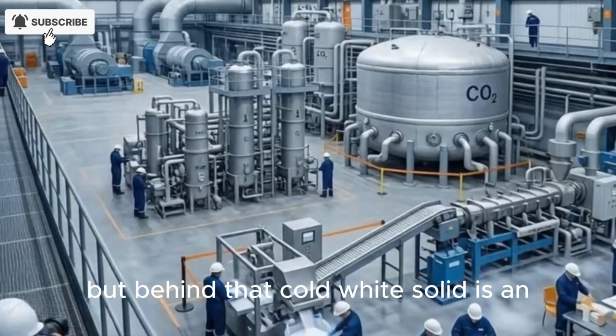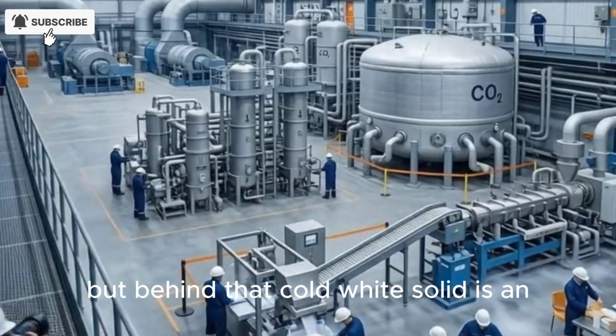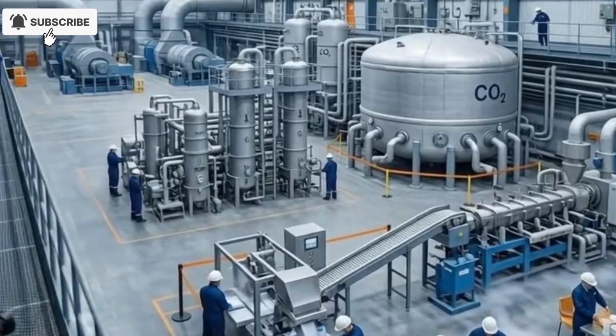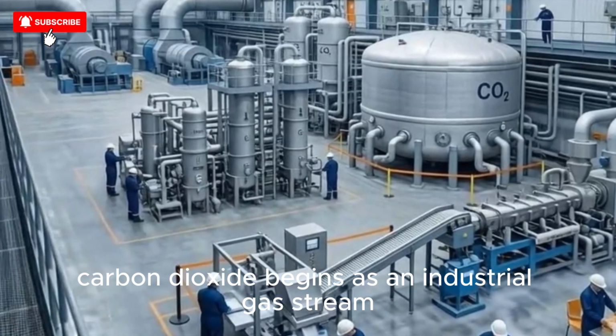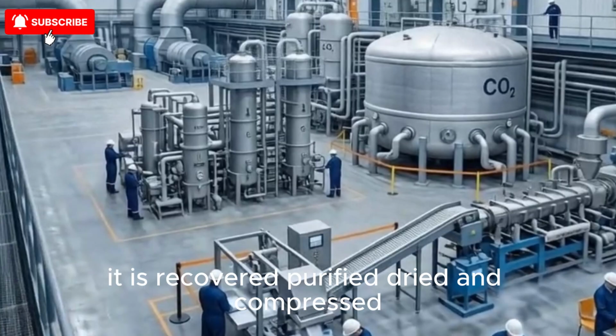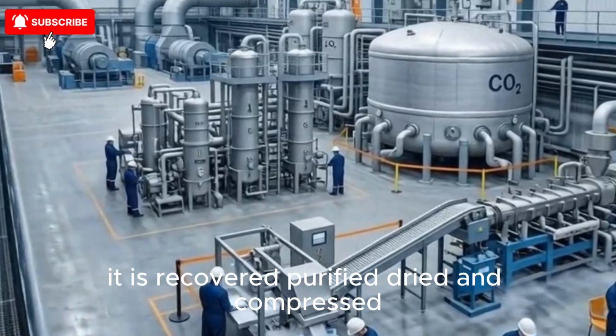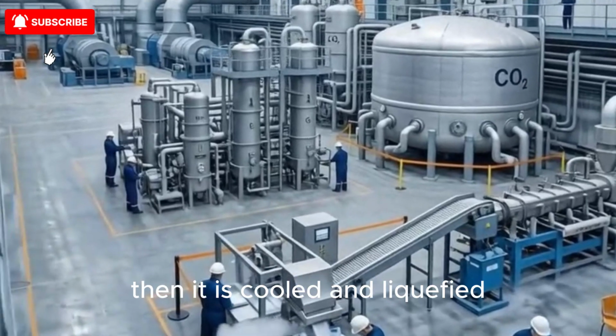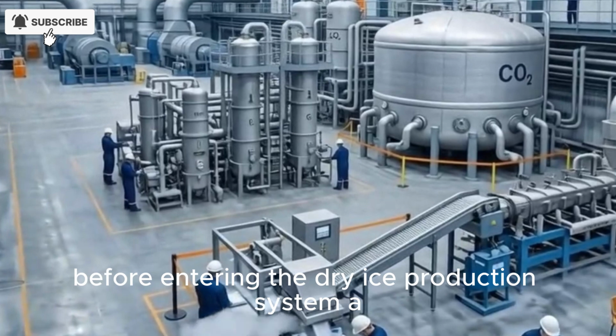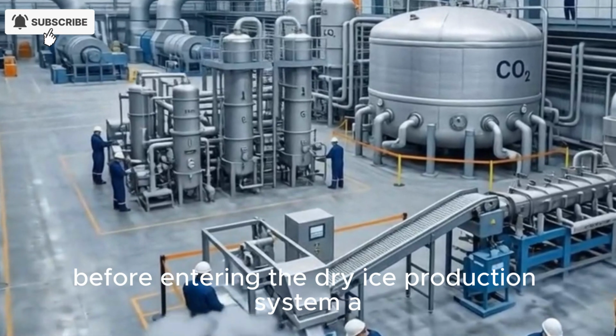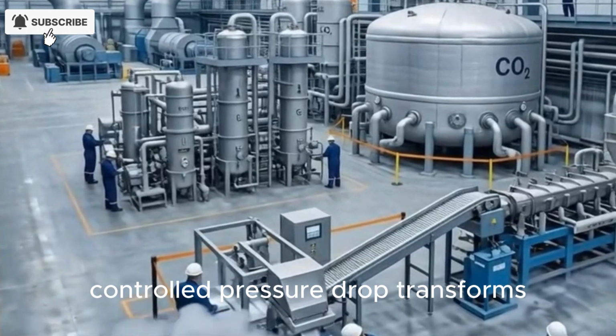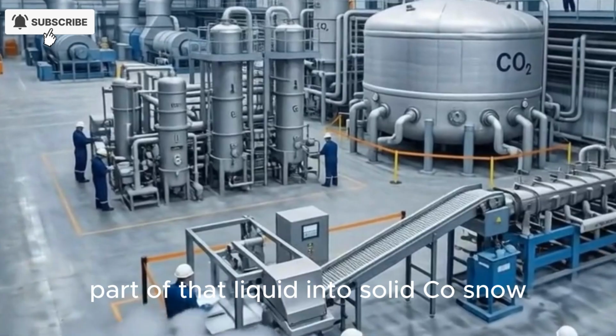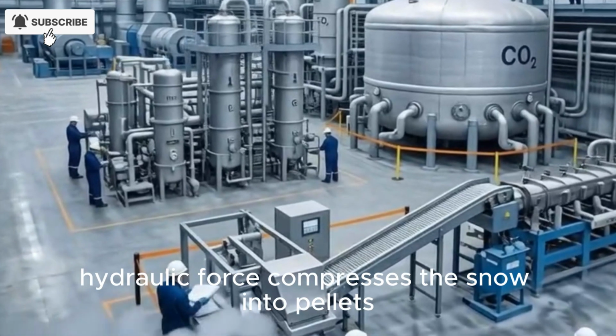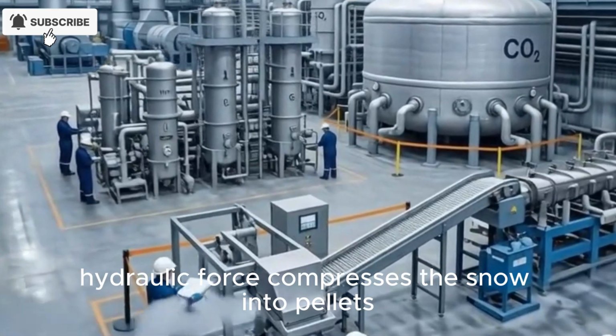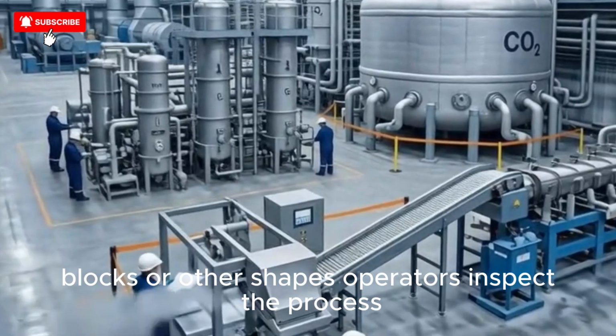A piece of dry ice may look simple. But behind that cold white solid is an entire chain of engineering. Carbon dioxide begins as an industrial gas stream. It is recovered, purified, dried, and compressed. Then it is cooled and liquefied before entering the dry ice production system. A controlled pressure drop transforms part of that liquid into solid snow. Hydraulic force compresses the snow into pellets, blocks, or other shapes.